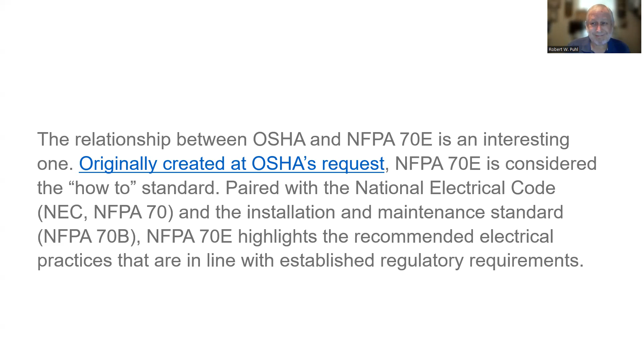Is NFPA 70E the regulatory standard? No. But is NFPA 70E compliance required by OSHA? Yes and no. We're going to finish this conversation about that too. Legally, the NFPA 70E standard is considered an industry consensus standard used to assist OSHA in preparing electrical safety standards. This means it is not directly incorporated into the Code of Federal Regulations. As you know, there's a lot of stuff incorporated by reference into OSHA standards. This is not. Seems odd to me that it isn't, but it isn't.